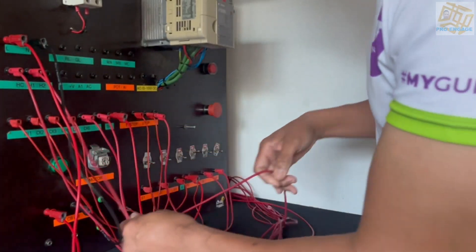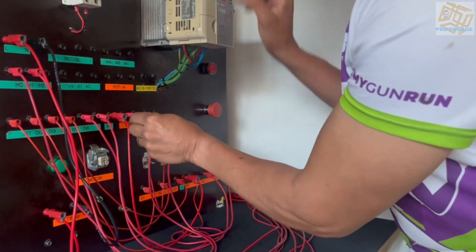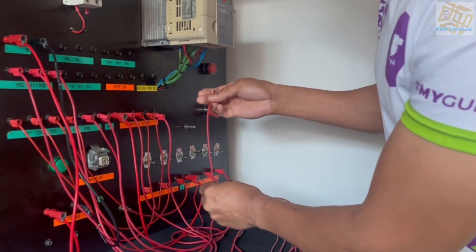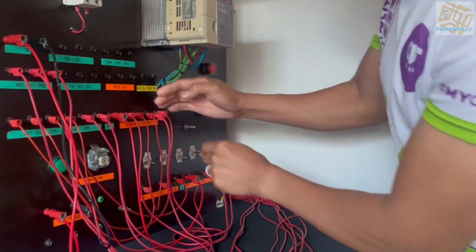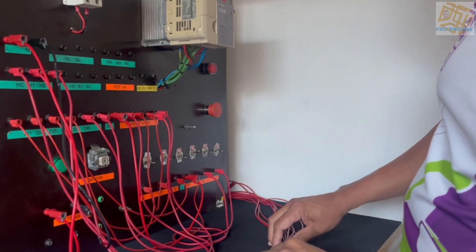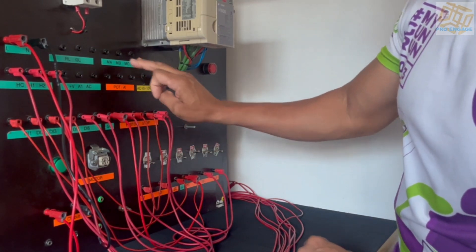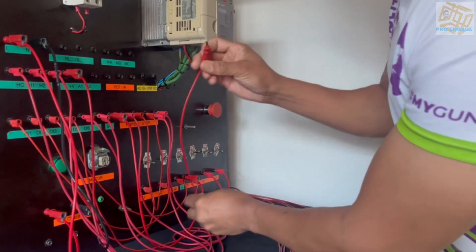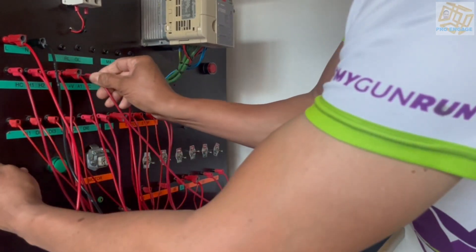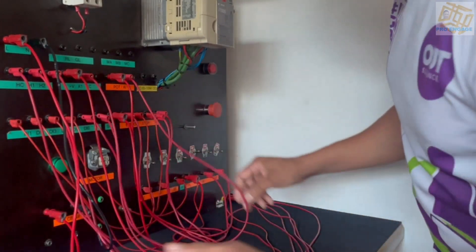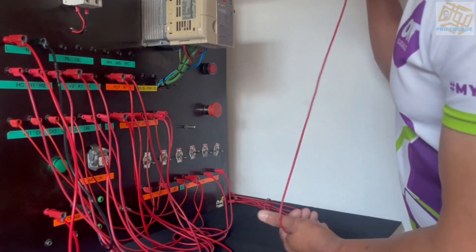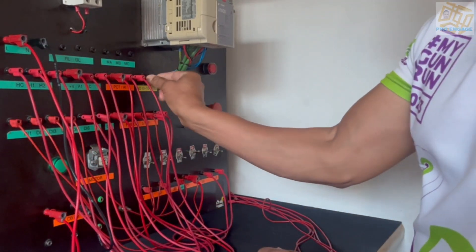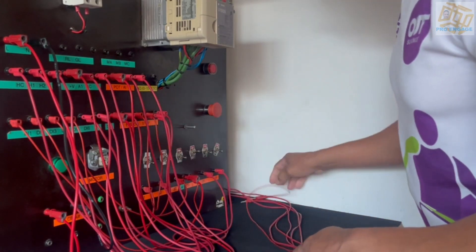I found the HC which is the loop and I've looped the e-stop and the stop. I've connected my e-stop and stop buttons. You will find that when the system is running, these buttons produce a particular fault displayed on the VSD screen. Now I want to see where my pot connections are. I don't have much left now. If you can identify A1, then you've done the most. Once A1 is connected the other two points don't matter because the end points of the pot don't matter which one goes where.